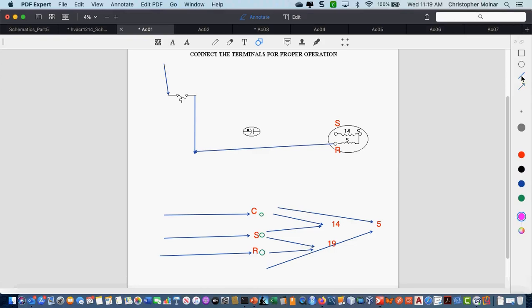Your start winding, on the other hand, if there is a capacitor, always is in series with the capacitor, and I'll explain why in a minute. So what we do is we put the start winding in series with the capacitor. Common always comes back to neutral. Okay, so I'm going to label that neutral, and I'm going to label that line.